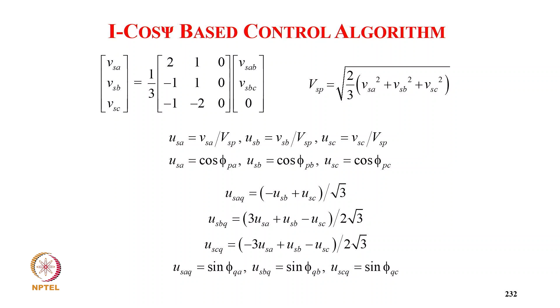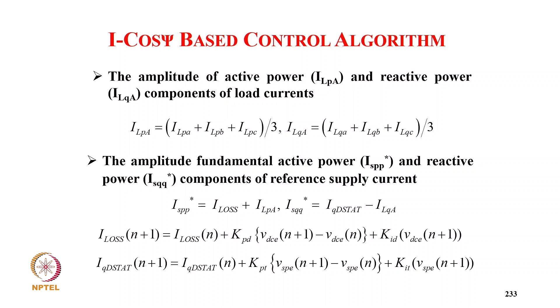This is the algorithm. So we get the phase voltage from the line voltage, then the peak value, then the template, and from the template we get the quadrature template. And then we typically get the average components of the active component and reactive component. Then we use the amplitude voltage control with the loss component for active DC link voltage control, and for AC voltage control we have a quadrature axis component PI controller. So these are the PI control equations.